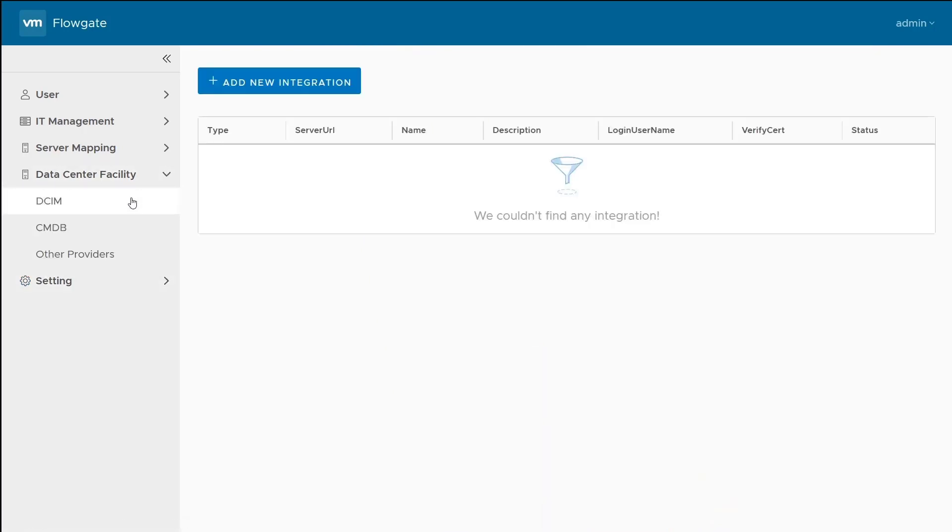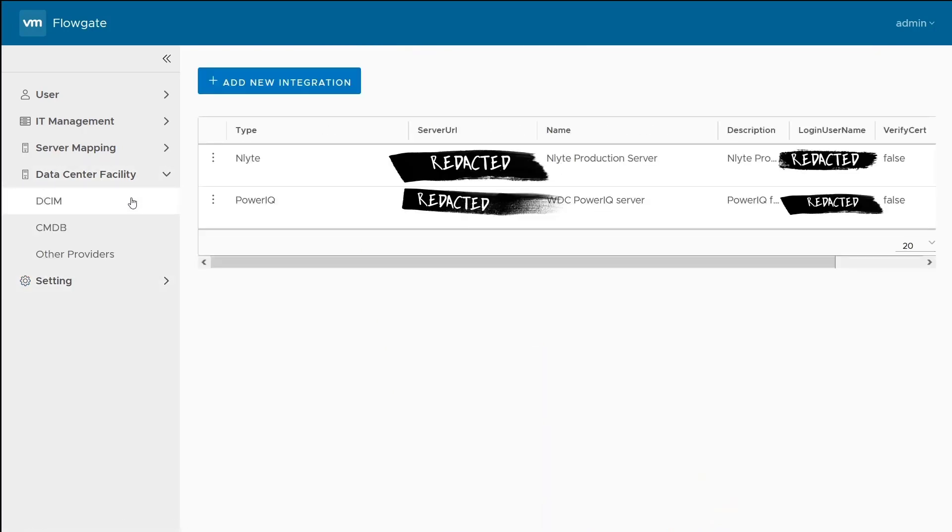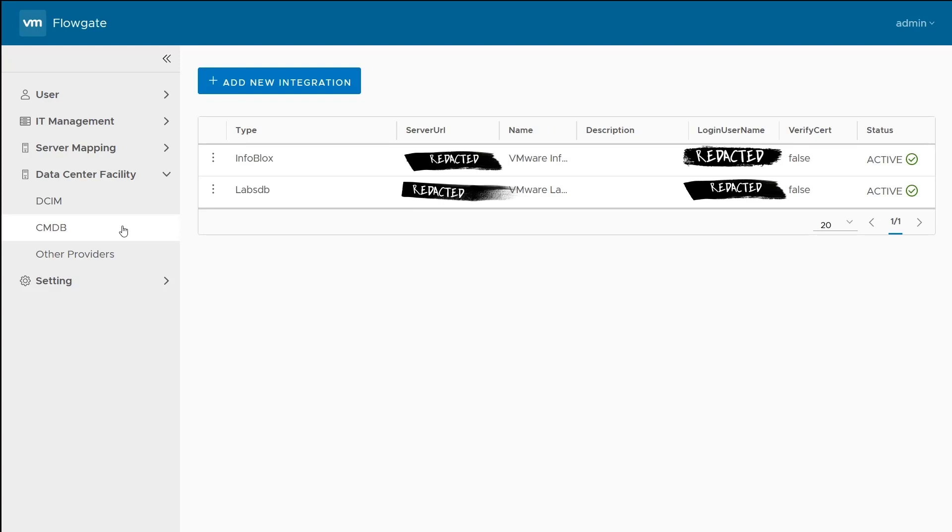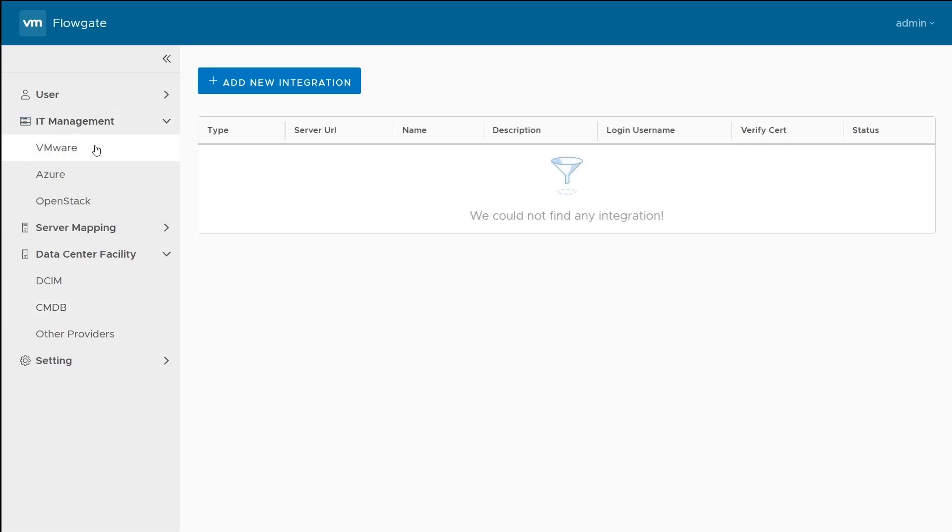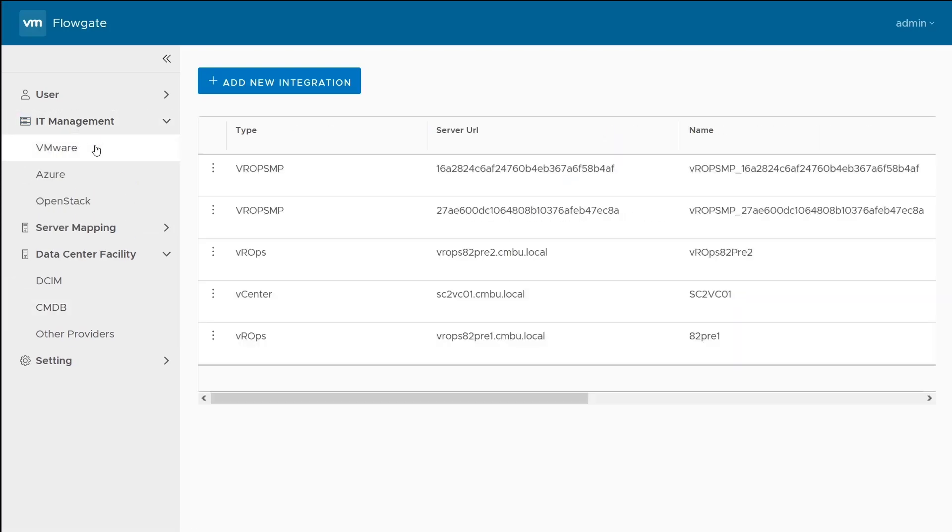If we take a look at our DCIM connections, we can see we have data flowing in from Nlyte and PowerIQ. Nlyte is giving me all of the temperature and humidity data throughout the data center. PowerIQ is feeding me power usage from each of the PDUs. This data is then correlated with data coming in from our CMDB, so we know exactly where each server lives within the data center. We're also pulling in objects from our vCenters and vRealize operations, which is configured up here.